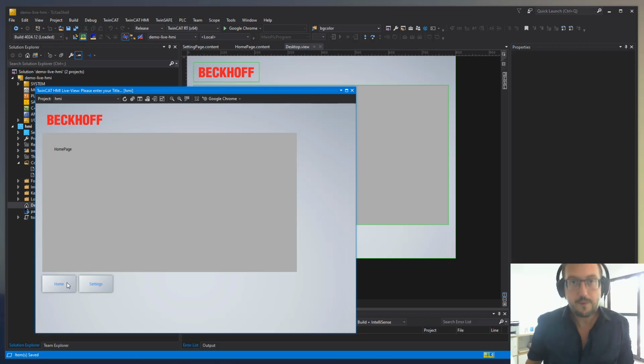So a couple of things that we've learnt here. Firstly, desktop view, you can class that as your base view. That's the thing that people hit when they're going to view your HMI. So don't worry about swapping too much between views, because views are kind of core. You can swap between views, but you need JavaScript to be able to do that. So there's no easier way to swap between views, although it is completely possible. That's not a problem. But really just keep view as being one of your bases. That's where you're going to live. If you want pages to swap out on top, you'll do that using regions and content.